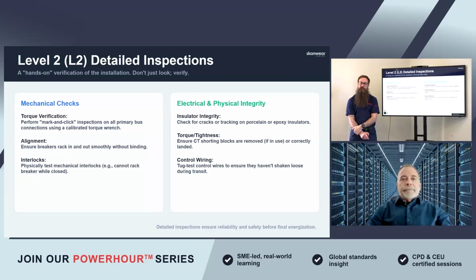Next slide. Yeah, I mean, just to add into that, we're talking about your pre-energization checks, so your level 2 stuff, which again we link a lot with the first commission and first energization processes. But in reality as well, this is so true for post-maintenance, post-fault. These are all areas that, again, it's not often an electrical issue, not putting down the mechanical guys, but typically it's normally a mechanical fault which causes shorts and arc flashes, things like that. So the torque verification piece is equally as important after that point to make sure we haven't got any loose connections and things like that, alignment checks. So all these things, although we're saying the level 2 pre-energization checks, it comes into play post-maintenance, post-fault, things like that as well.